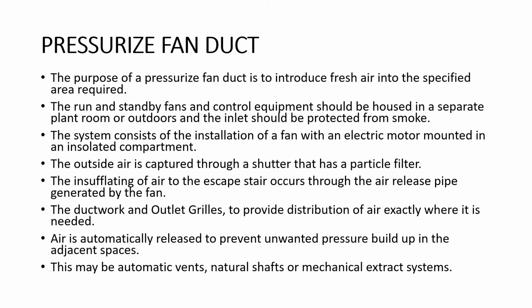So about pressurized fan duct. So what is the purpose of pressurized fan duct? The purpose of pressurized fan duct is to introduce fresh air into the specified area required. The run and standby fans and control equipment should be housed in a separate plant room or outdoors, and the inlet should be protected from smoke. The system consists of installation of fan with an electric motor mounted in an insulated compartment. The outside air is captured through a shutter that has a particle filter.